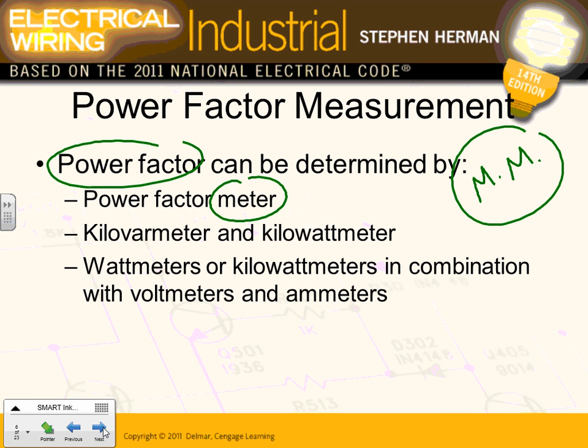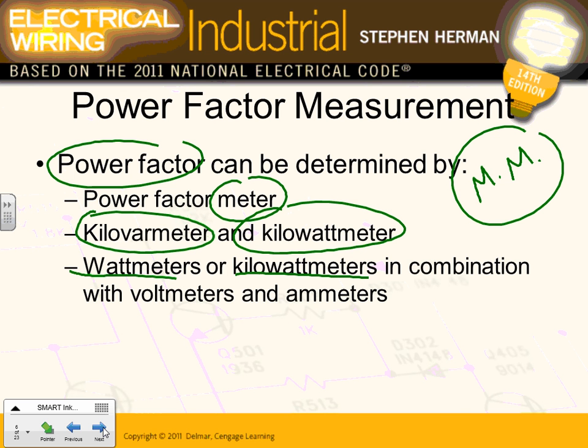Okay, so you have power factor, or you can have a kilowatt hour meter and kilovar meter that also gives you the power factor. Or you can have a watt meter and kilowatt meter in combination with a voltmeter and amp meter. That also can give you the power factor. Any comments, any questions about how to measure the power factor? Now, the common thing therein is to have a power factor meter.